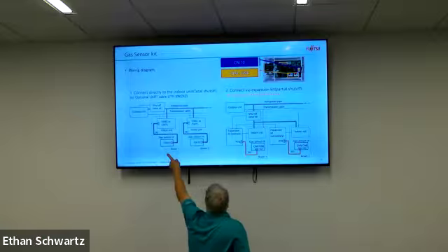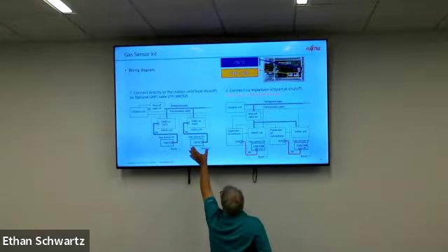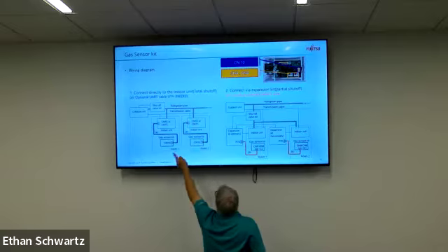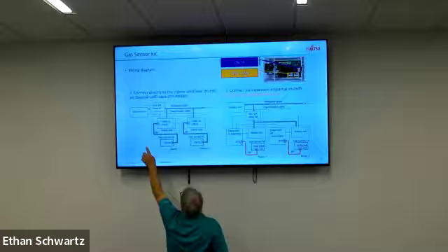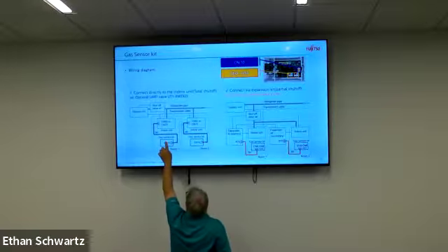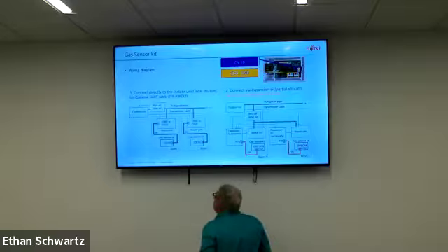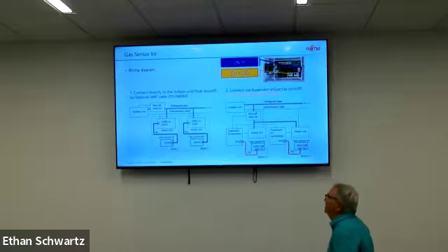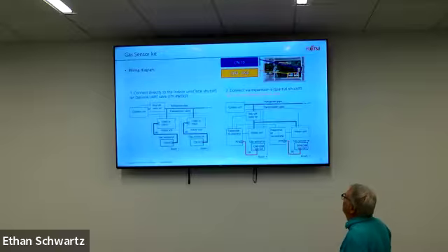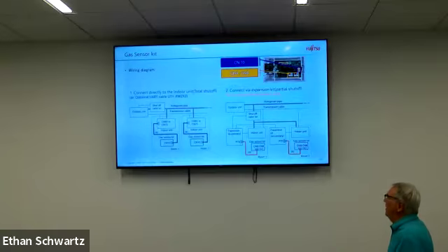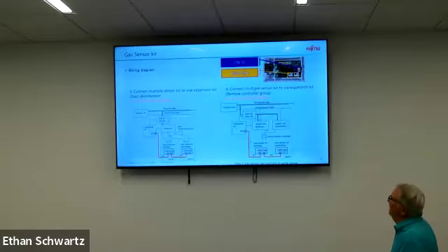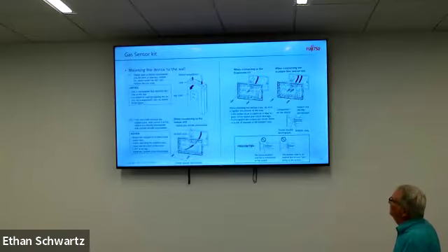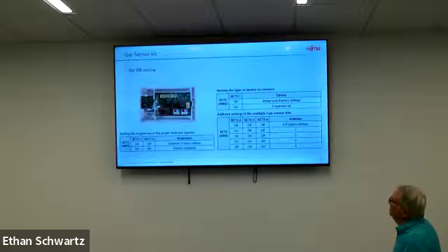Shut off valve kit at the outdoor unit with 2 indoor units and their gas sensor kits connected in, and then connected back to the shut off valve kit. We don't have a direct connection from the indoor unit to the shut off valve kit because the sensor is going to record it and create an error message in the indoor unit. That's kind of how it works. So I just wanted you to have a little bit of that. And then there's more examples, but I don't want to go much farther than this, just so you can see what's happening.